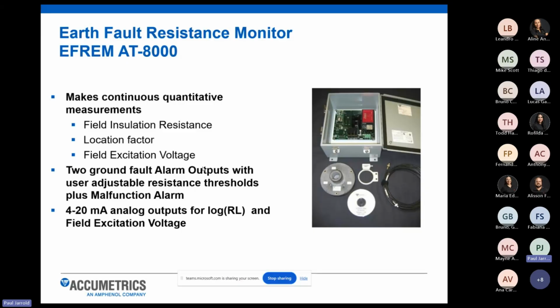And then lastly, a big advantage of our system is that we provide you an ability to trend the value of that field resistance and field voltage over time using 2 channels of analog outputs that are a 4 to 20 milliamp current loop output. So that oftentimes gets connected to a customer's DCS or control software and allows the customer to predict and trend the value of that resistance so they can monitor it over many years and look for that value of resistance to slowly drop over time.